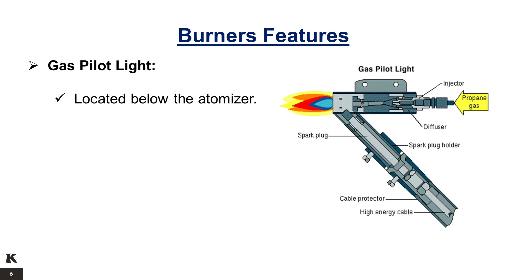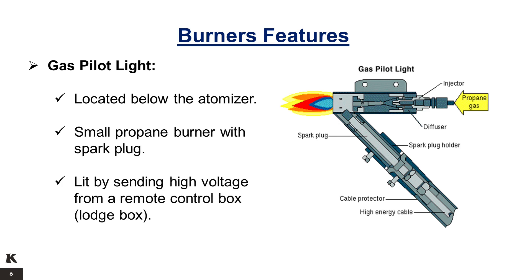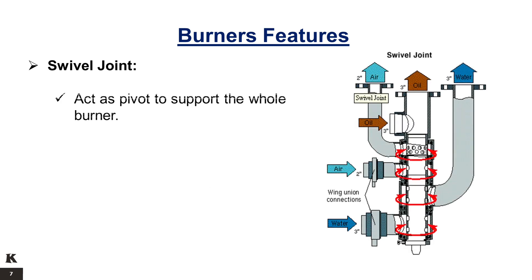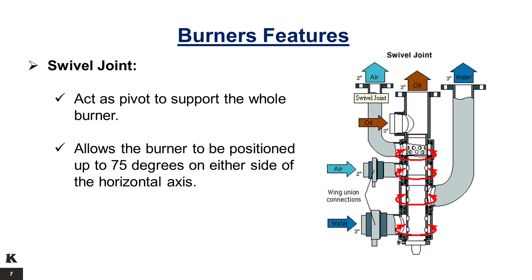The gas pilot light is located below the atomizer. It is a small propane burner with a spark plug, lit by sending high voltage from a remote control box or lodge box. The swivel joint of the burner acts as a pivot to support the whole burner, allowing the burner to be positioned up to 75 degrees on either side of the horizontal axis.